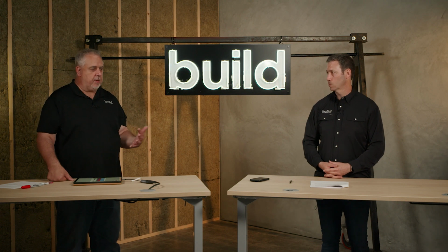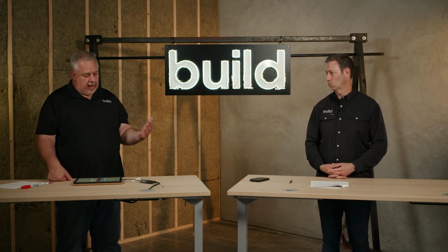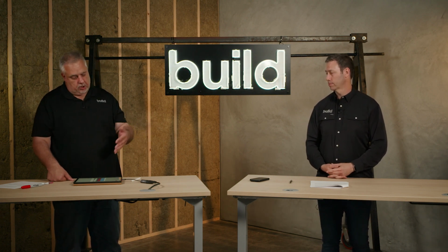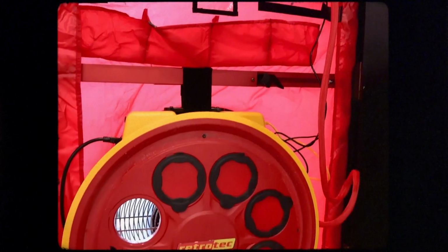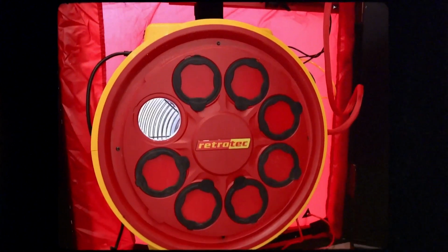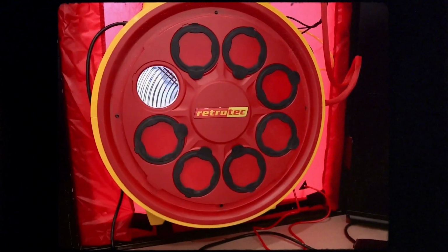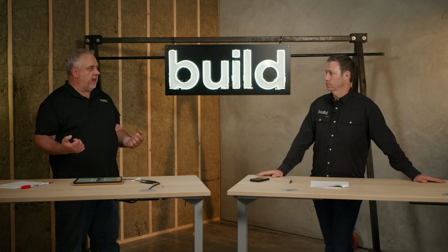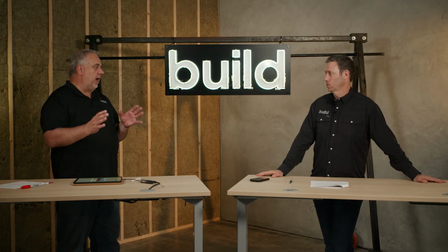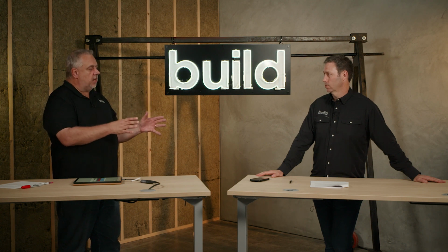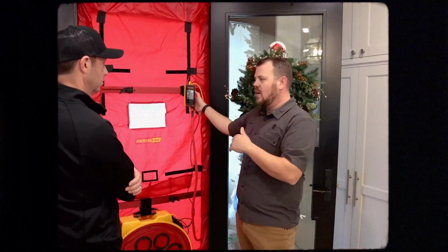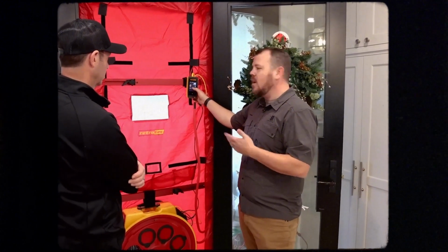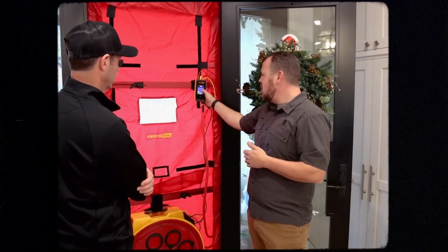Well, it just so happens that the building industry has verification systems. And in terms of air management, we have what we call blower doors. A blower door is basically taking the house to a certain pressure, measuring the air across the fan at that pressure, and then being able to identify how much leakage the building is having at that point based on calculations of the volume of the building.